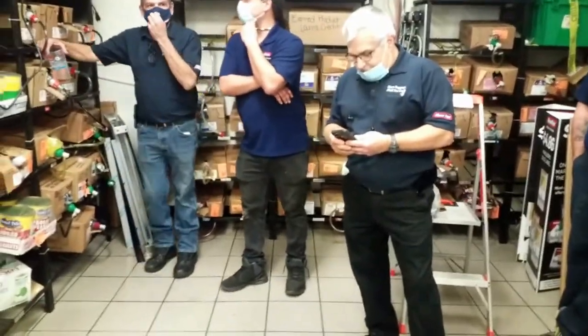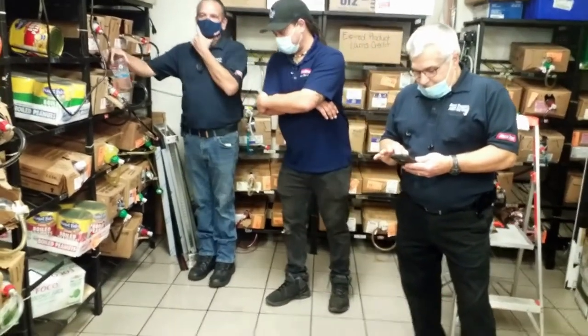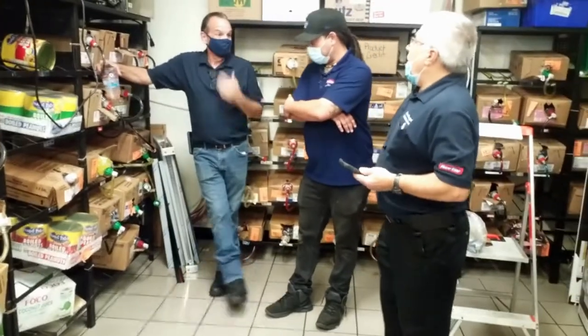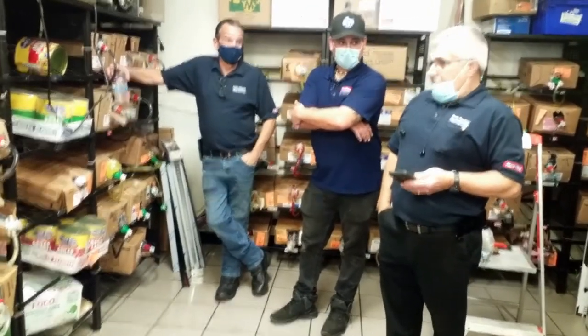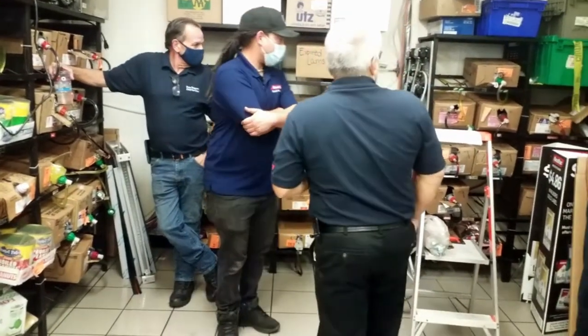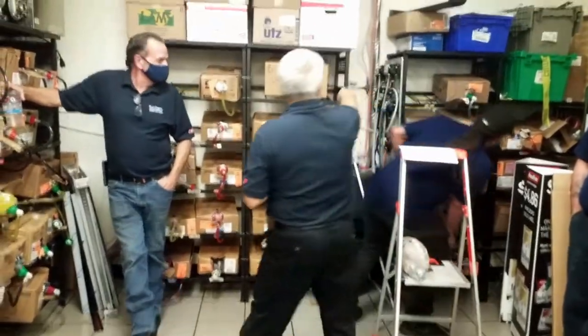It can happen. So if you go out and you see one that looks like it's blowing the bag up, you better change that pump. Right. So the other thing that can happen is the changeover valves, where you can hook two bags up. Right. The little button that pulls.